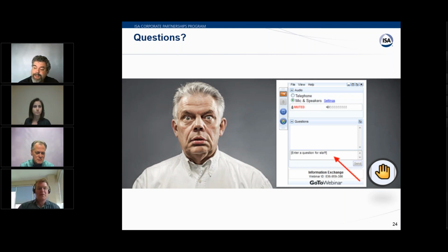Well, it's Ian here. The other guys might have more to say, but generally I would just stay with where you are, the 4 and 7, because you're doing the right thing. You're spanning your expected measurement range. You're always going to stay acidic, so you're not going to change from an acid to an alkaline or vice versa. So you have the right range. And just because you're near the end, as we've seen, the response tends to be quite linear. So as far as I believe, you're doing everything right. Yeah, and 2 points saves you time, instead of having to rinse a third time. So good practice.